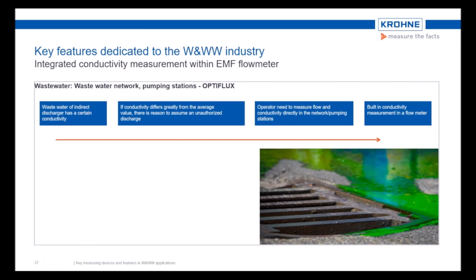Operators of sewage treatment plants and sewer networks use inductive sensors to measure electrical conductivity. This comes at considerable expense. In addition to the investment costs for the analytical conductivity measuring device, there are installation, wiring, and maintenance costs to consider. Electrical connectivity is generally measured at pumping stations, gauge valves, and sewage treatment plant intakes. Flow meters are also usually installed at these locations. Today, the measurement task can be fulfilled by the already installed EMF meters through their integrated connectivity measurement. So the Optiflux 2300 electromagnetic flow meter EMF simultaneously measures flow and electrical conductivity.